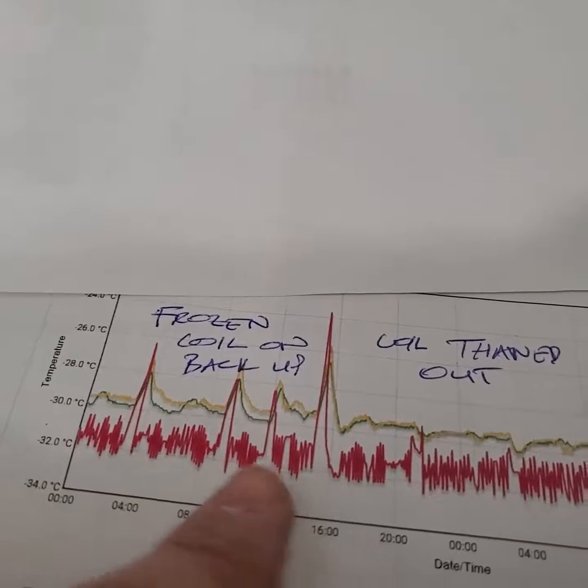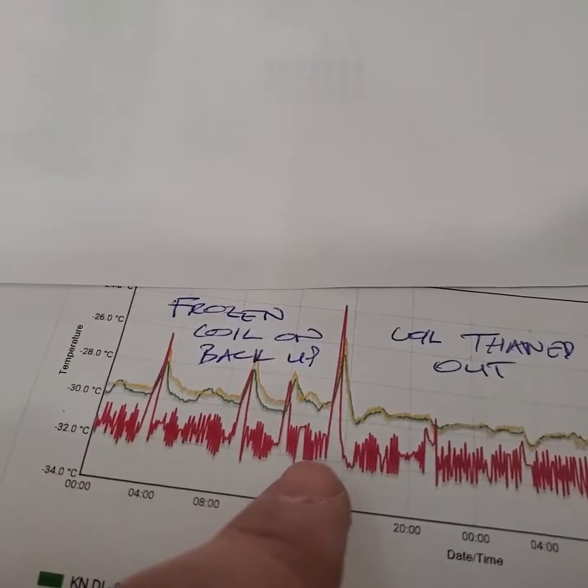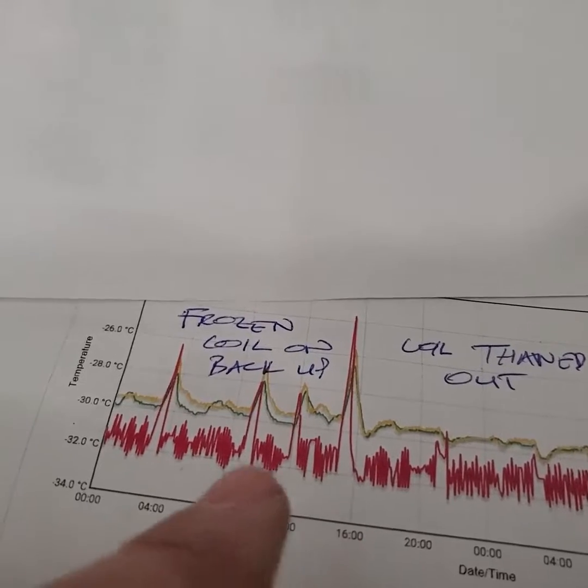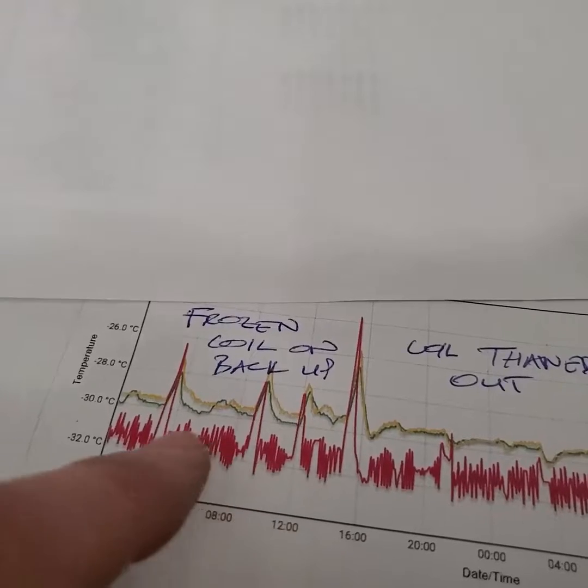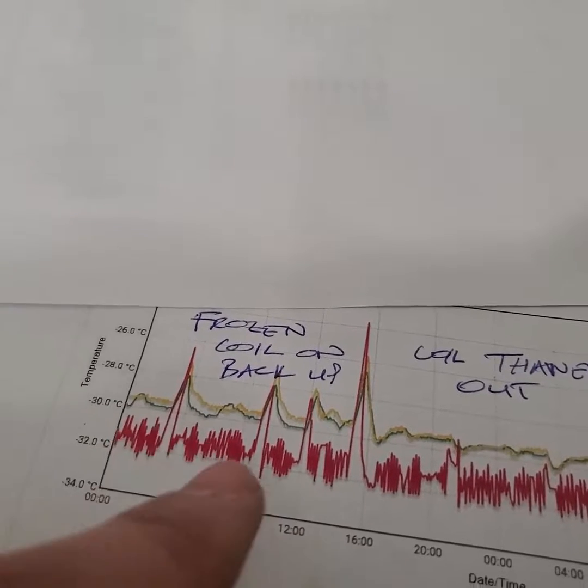This trend log shows yesterday up until about 4 p.m. What happened here is I had a coil blocked with ice because one of the fuses for the defrost heaters was blown.